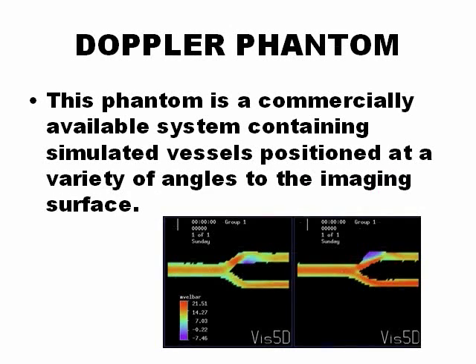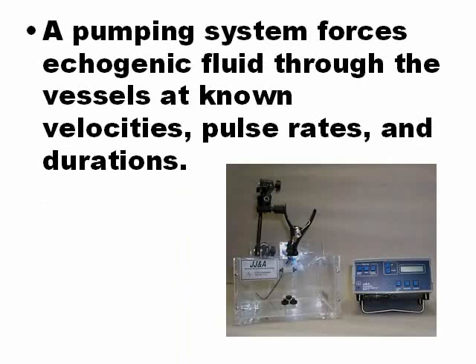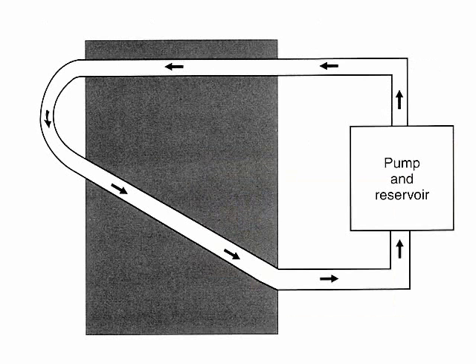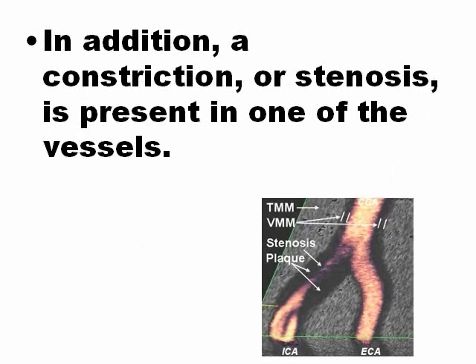The Doppler phantom is a special phantom to evaluate the Doppler function of the machine. This has a pump moving a fluid that is similar to blood, and you must recognize if the velocity in the machine is the same as the velocity in the phantom. You can see here the schematic picture. A pump moves a liquid similar to blood, and with the transducer you measure the velocity of this liquid, and you can see if your machine is making accurate Doppler measurements. In addition, there are some stenoses, and you can measure the high velocity and the aliasing in these areas.